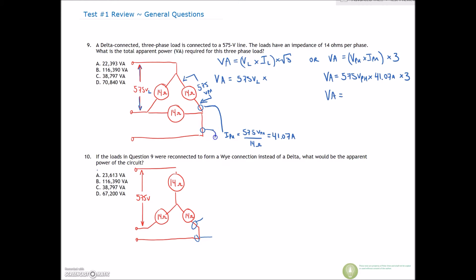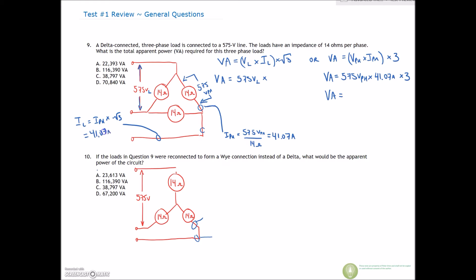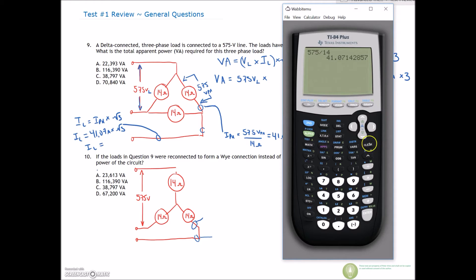Continuing on to find our line current. We know that our line current equals our phase current times √3, which is 41.07 amps times √3. I-line equals 41.07 times the square root of 3, which gives us 71.135 amps.